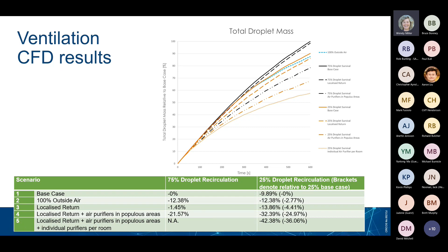So this graph shows the net suspended aerosols after 600 seconds or 10 minutes, with the outside air shown as the dashed blue line. The best results come if you assume a 25% droplet survival rate and you have individual air purifiers in each room. These are the percentage reductions compared to the base case, shown in the table below. If you assume a 75% droplet recirculation, your best results are having localised air return and air purifiers around your nurses' station, or the localised return and air purifiers in each individual room as well. You can read the details of that in the full report.